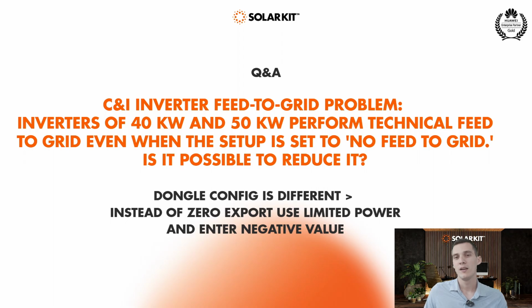And this would leave the inverter with a tolerance zone, so if a consumer is turned off, then the inverter can start to reduce its power output, but because it had an extra 100 watt buffer, let's say, it has a bit more time to reduce its power and the energy will not flow back into the grid. You need to find the correct amount from site to site.